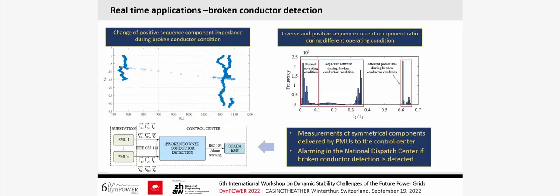Also, one real-time application that I mentioned before is broken conductor detection. We use symmetric components of the voltage and current for detection. And the important thing to say is that this works very precisely when the PMU is installed on the power line. When the PMU is close to the power line with a broken conductor, we can see a rise of unbalanced operation close to this PMU. So it can be a warning and it can be an alarm. I don't want to talk long about it.